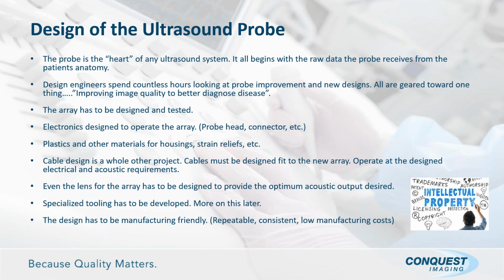Not to pick on the cable, but the actual diameter of the microcoax varies in these ultrasound probes depending on the array and the frequency the array is operating at, and a lot of that is due to signal loss or noise. One of the things, and we'll touch more on it, is that a lot of people tend to think the lens on most ultrasound probes is just a base silicone material, and a lot of them are. It's a compound, but that's got to be designed. They're looking for the optimum acoustic output, or throughput even, of the lens. Again, you don't want signal loss. So believe it or not, there's a lot of design work that goes into the lens, and I'll show you ways they test for that.